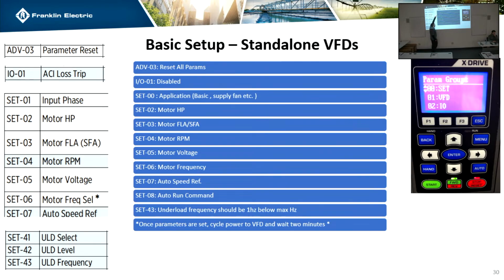The motor horsepower is going to be defaulted to the size of the drive. The motor FLA should be from the NEC chart of that horsepower. The RPM is going to be defaulted at 3,600, I believe. Voltage is going to be defaulted at whatever the drive is. Motor frequency is going to be 60. And then you'll always need to set 7 and 8 for how you want auto to work. And then I think 9 and 10 are hand. So those are the ones that you need to go through.